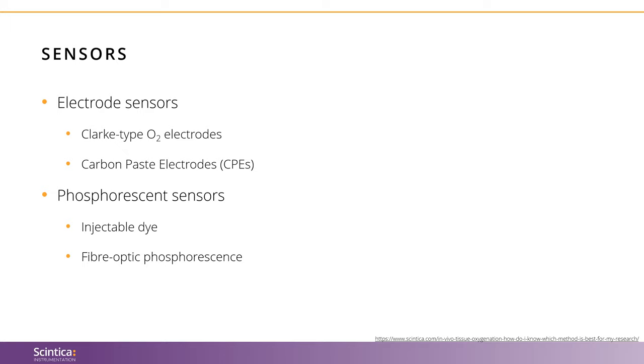Carbon paste electrodes work similarly to the Clark by creating an electrical current, but these sensors use a graphite silicone paste mixture that interacts directly with tissue of interest to generate the current. Compared to the Clark-type electrodes, CPEs are less sensitive to temperature at the measurement site. With phosphorescent sensors, oxygen efficiently quenches the fluorescence and phosphorescence of certain luminophores, a process also known as dynamic fluorescence quenching. This quenching process is based on the principle that molecular dissolved oxygen in tissues or fluids can terminate or quench light emitted by a fluorescent compound dye. The extent of quenching is directly proportional to the partial pressure of oxygen in the vicinity of the dye.